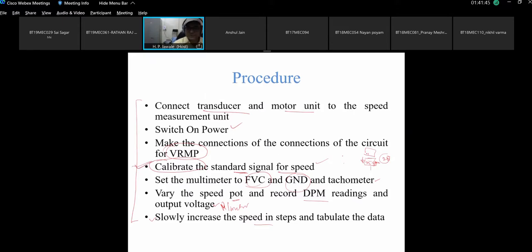For 0 speed, it should show 0 RPM. For larger speed, say for example on the motor, it is at 25 RPM. When I am going to have the speed knob to the full of its indicating value, it should show the largest value. If it is showing 32 RPM suppose, then I need to reduce the gain so that it will come down to 25 if it is the highest speed at no load. That is called as the calibration. This is something new into this.